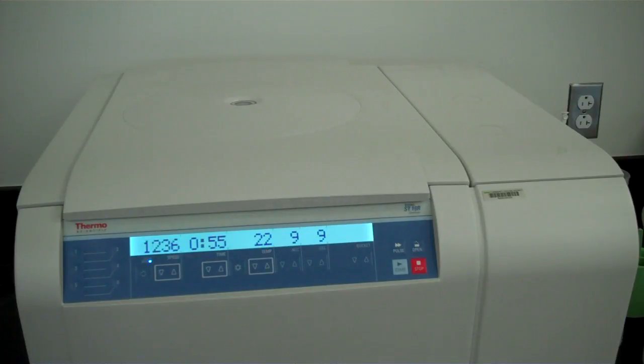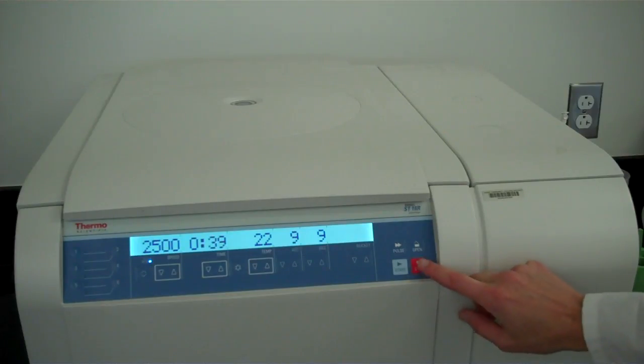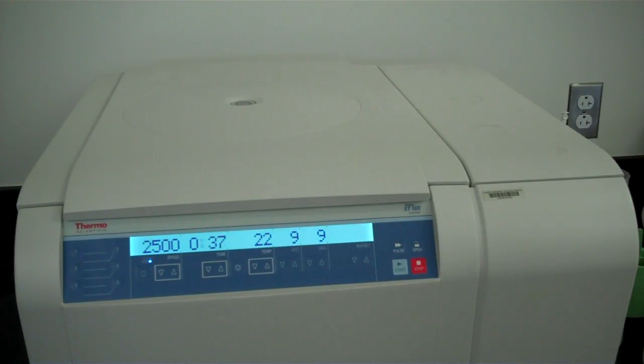Now once you press start, you must stay by the machine until it comes up to the designated speed. If there is any imbalance, it will begin to make loud or alarming noises, in which case, because you are standing right next to the machine, you can go ahead and press the stop button immediately and hopefully limit the damage that you have done to the machine due to the imbalance. So you do need to stay by the machine until it reaches the final speed.